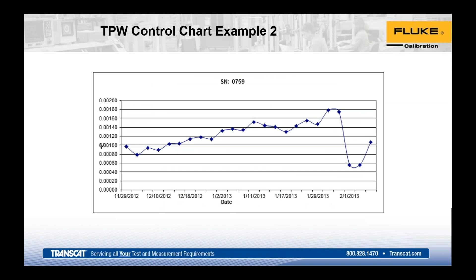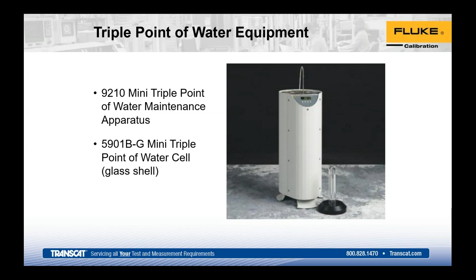So we're going to talk about the triple point. Again, really good, cheap insurance. Triple points are probably the most common fixed point used worldwide. They're relatively inexpensive compared to other fixed point cells. They're not as difficult to maintain or use, and you can typically get in the realm of 0.0005 C repeatability when you're using one of these. So again, a really stable, easy way to repeat that check. But you can also do an ice bath if it's built and maintained properly. The uncertainty will be slightly higher, but again, still good, cheap insurance.